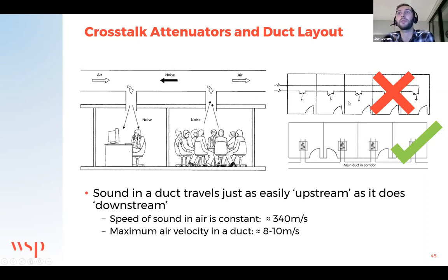In terms of the arrangement of this, looking at it on the right hand side, it's best to have these crosstalk attenuators generally in parallel, as shown here, rather than in series. If you do have the series approach, you get a lot of resistance or pressure as a result of each attenuator adding up in the system, whereas if you have this in parallel, this isn't the case in this example.